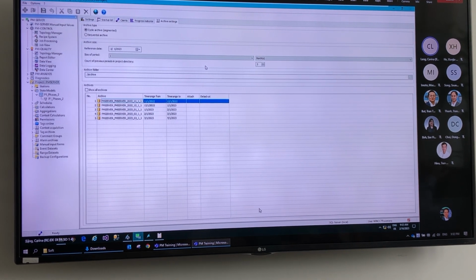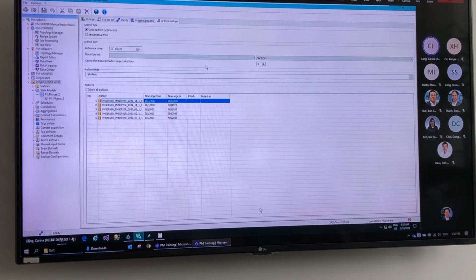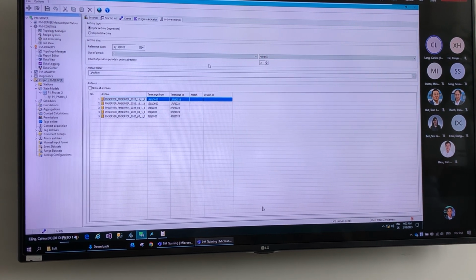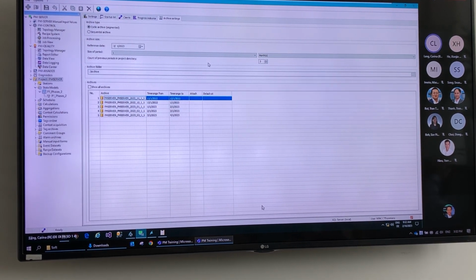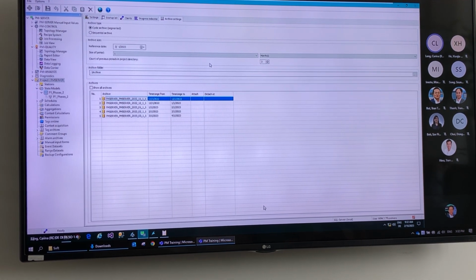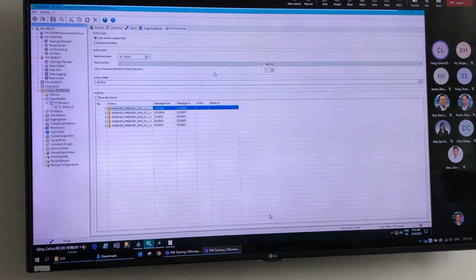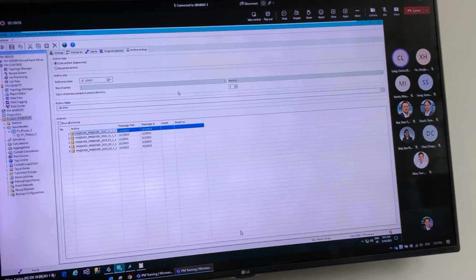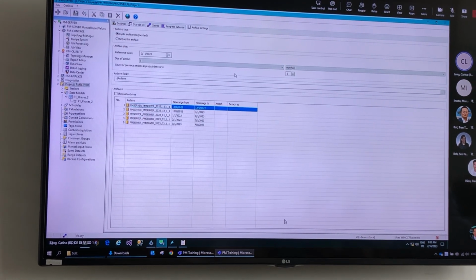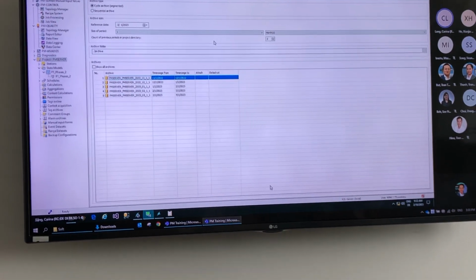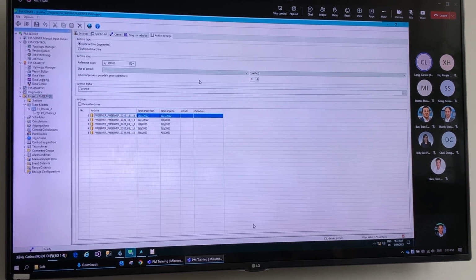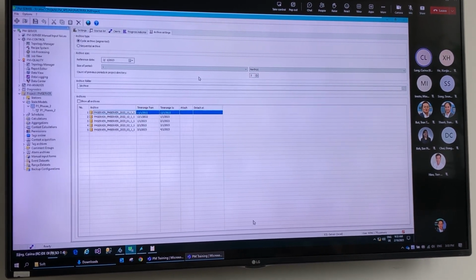So that means I have reported data where I do not have any archive for, so I do not get access to this data because there is no archive, so no database. I cannot store the data anywhere. And to prevent you from making the same mistakes I made when starting to work with that, just for information, if you want to import historical data, then be sure that your archive settings fit the time range for historical data too.